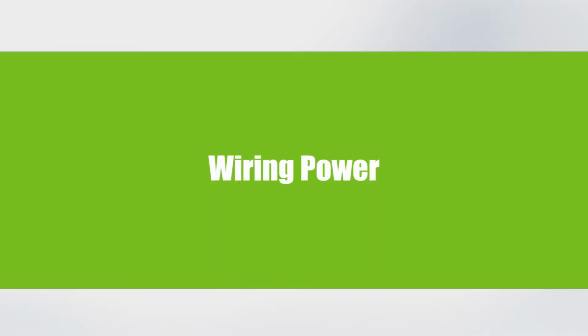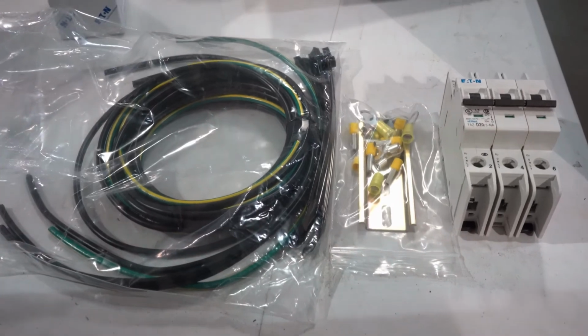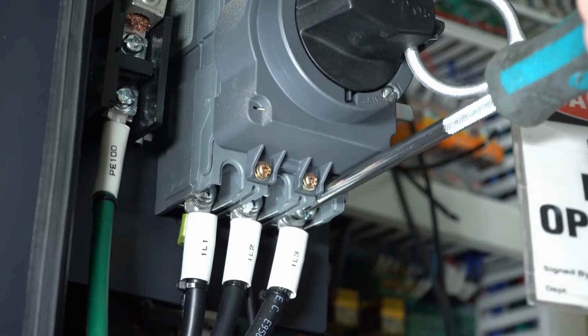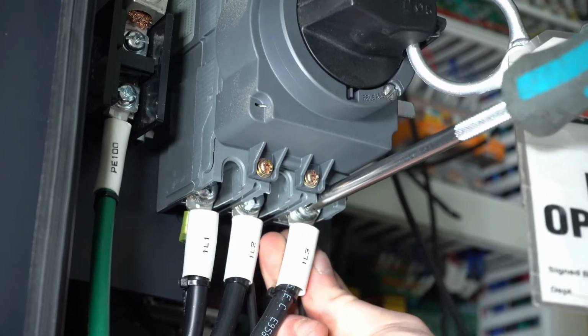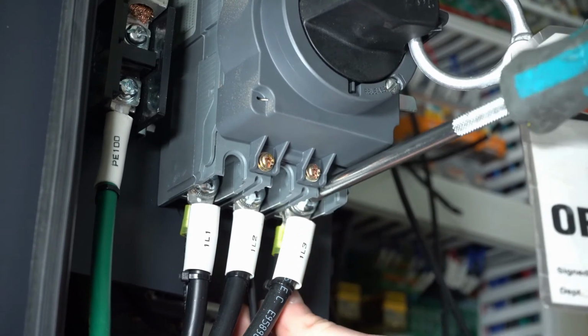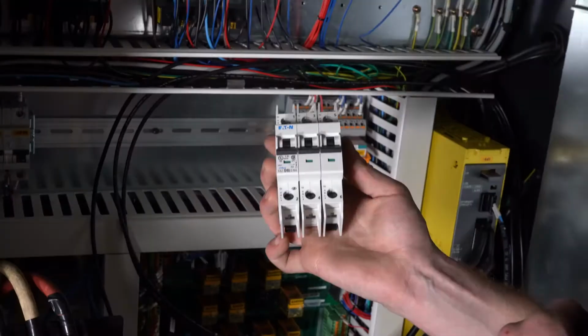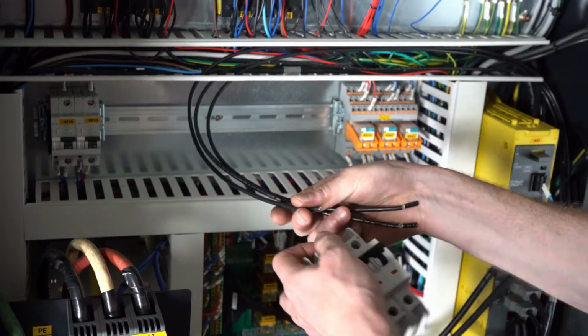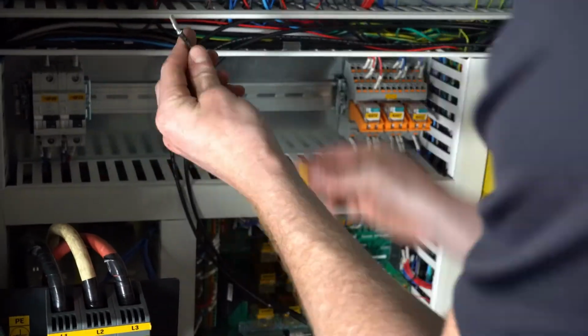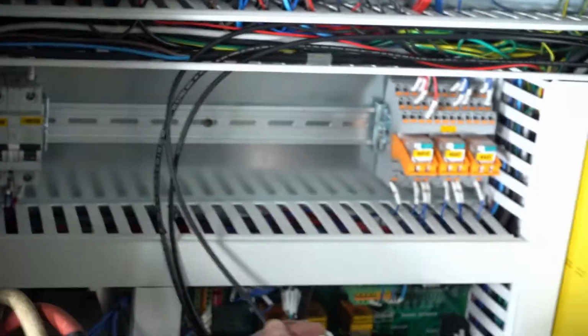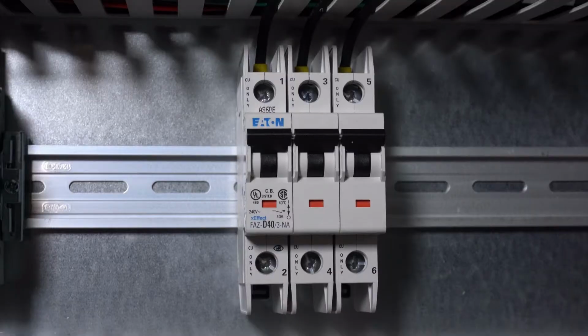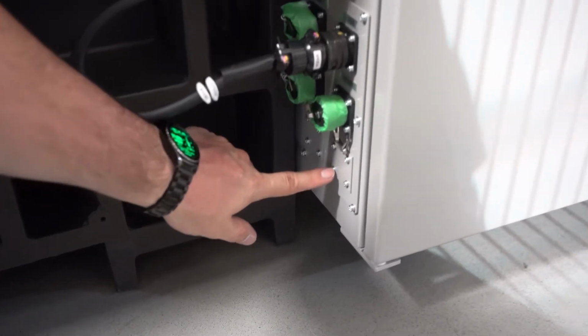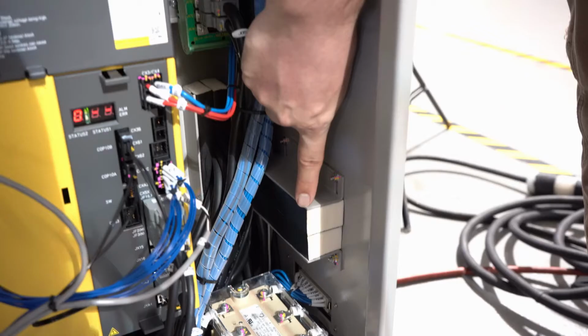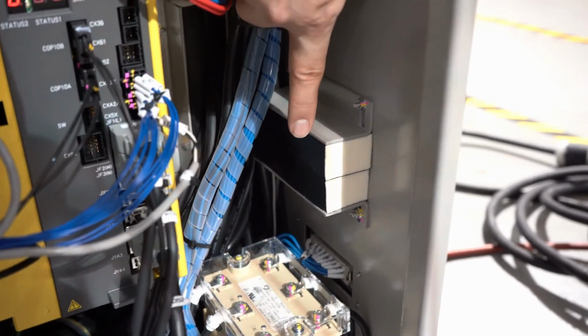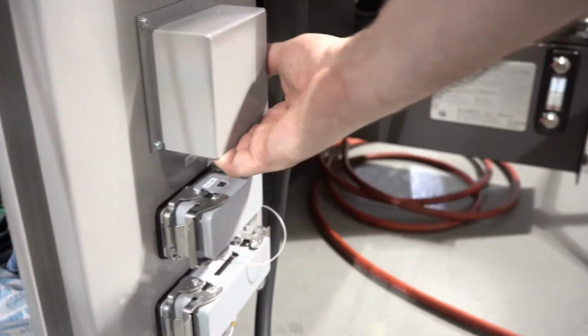Wiring power. In the kit, we provide a breaker kit similar to one that you might get with your high pressure unit. To install it, hook up the wires after your main disconnect into the top of the circuit breaker. Find an open section of DIN rail in the machine to place your breaker. If you can't find one, a small piece of DIN rail and a couple screws are also provided in the kit. Next, find a way to run the power cable into the machine. Shown here are a couple examples of either knockouts or soft seals that you can use.